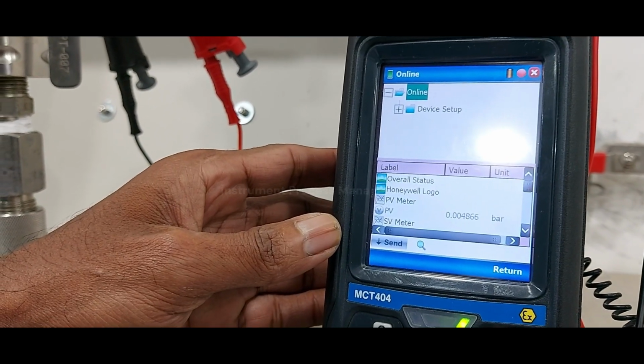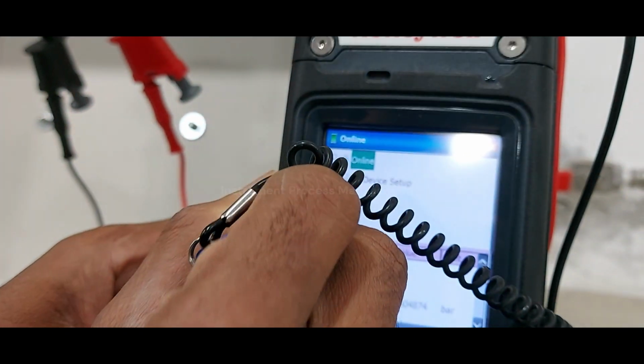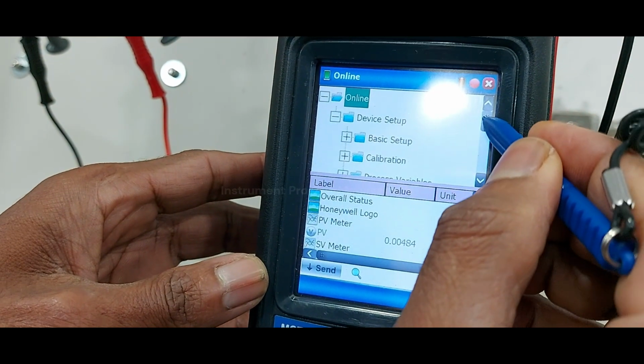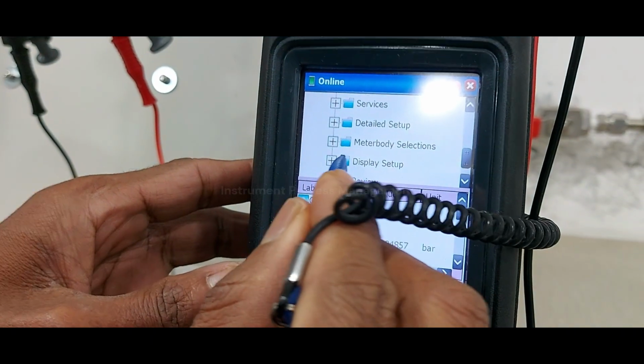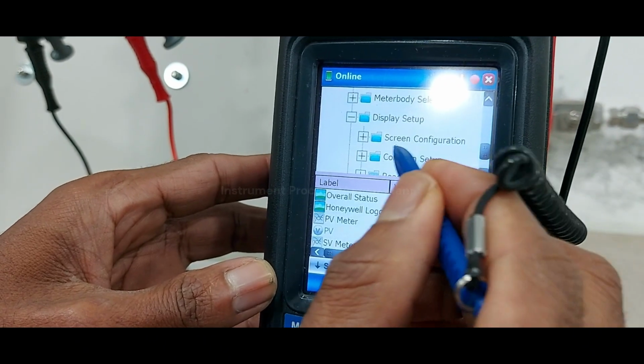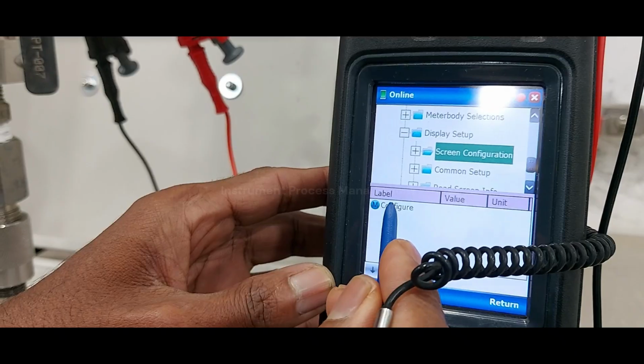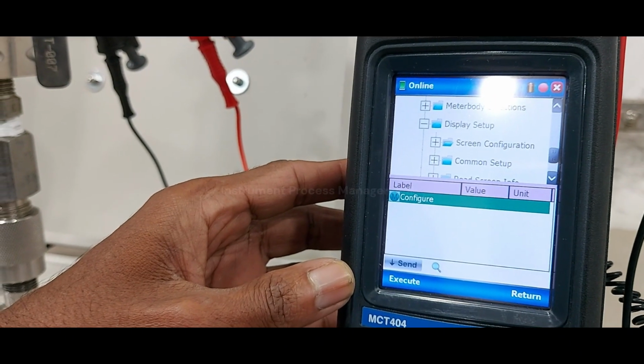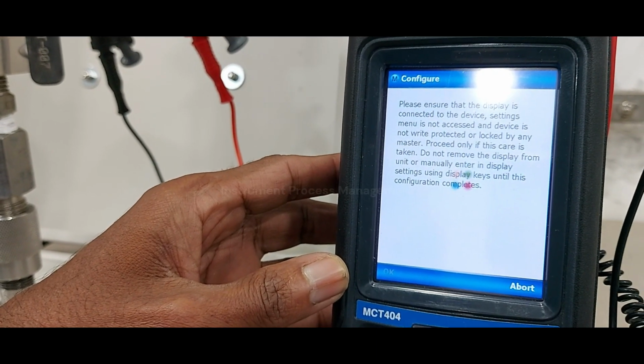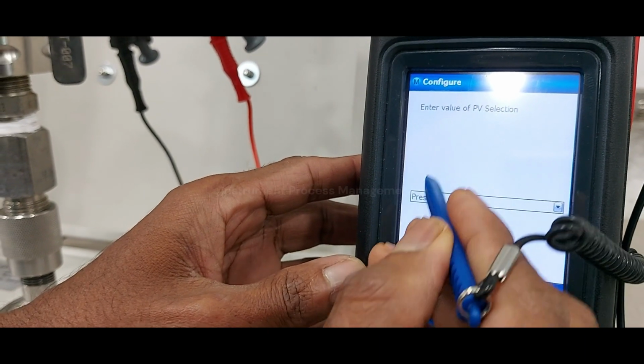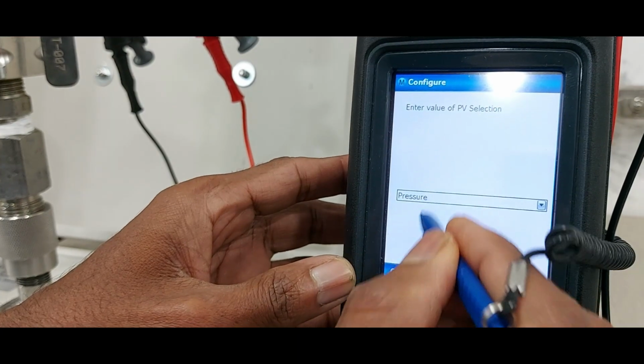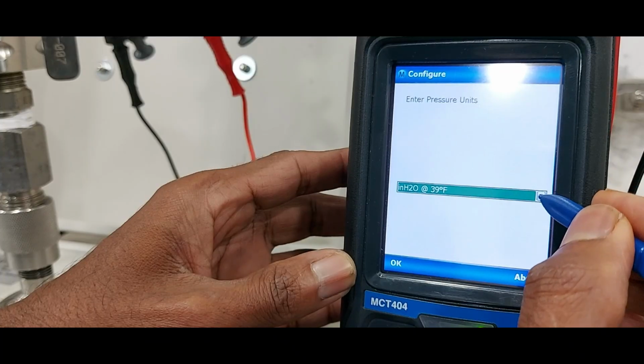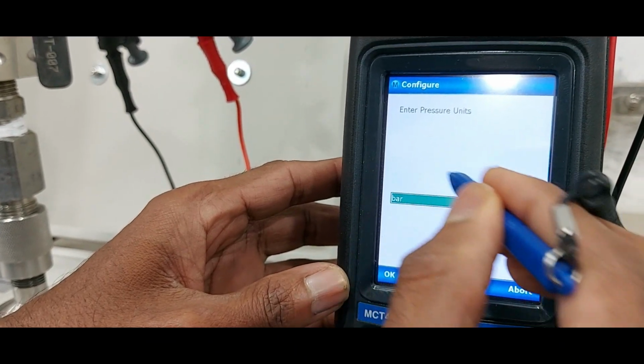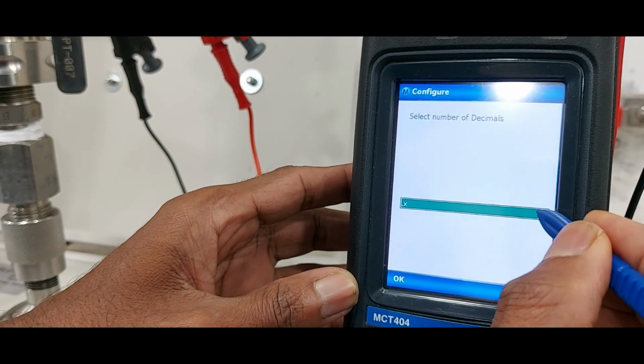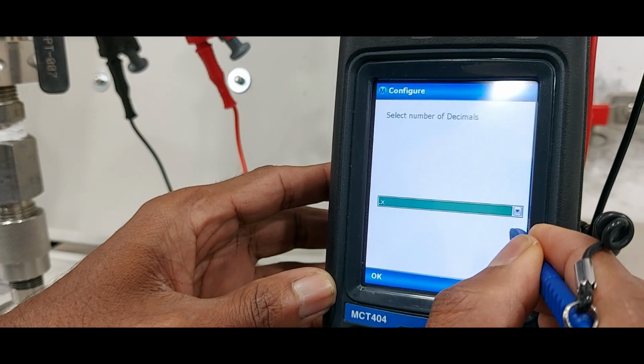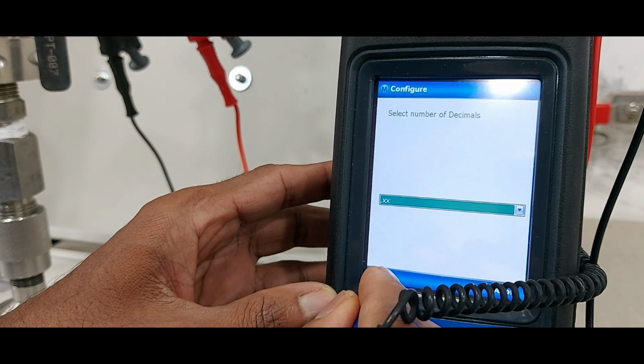First we are doing the display configuration. Select the plus button and the device setup, drag it down, display settings, select it, and the screen configuration, select it, and configuration and execute. Select the enter value of PV selection, that is pressure, fine. Select the unit is bar, select decimal point. We will select 2 decimal point, done.